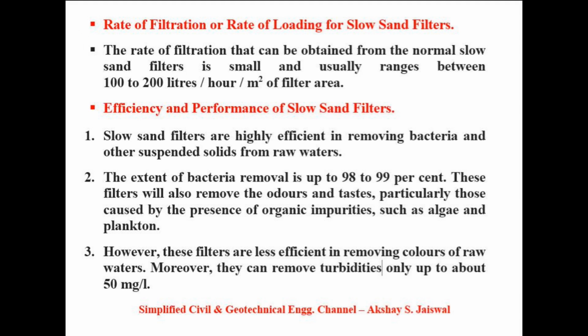Our next point is rate of filtration or rate of loading for slow sand filters. The rate of filtration that can be obtained from the normal slow sand filter is small and usually ranges between 100 to 200 liters per hour per meter square of filter area.